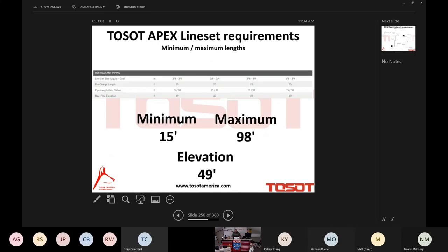Line set requirements. Minimum 15 feet, maximum 98 feet. Maximum elevation from the top of the outdoor unit to the indoor unit, 49 feet. Now, 15 feet, if you guys know our mini split product, that's different. Our mini split product, a minimum of 10 feet for each indoor unit, 15 feet here. I will tell you this, the primary reason for the 15 feet is that Tosot is concerned anything shorter, you may get a refrigerant velocity noise. Not the end of the world, and depending upon where the equipment is located, maybe not an issue at all.